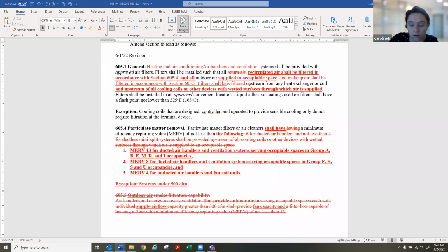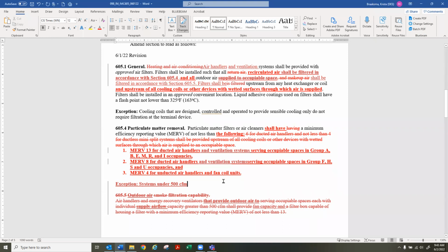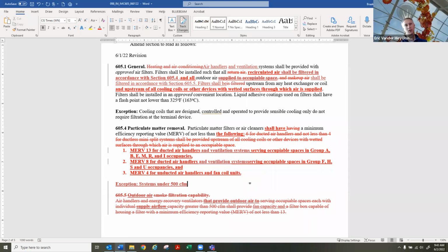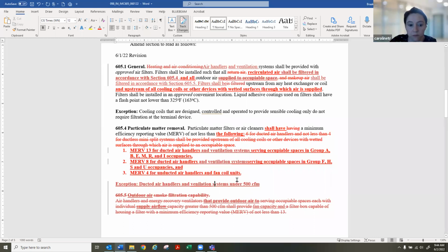Because essentially the MERV 4s aren't doing anything from a health standpoint. I'm assuming you don't want to exclude them from any filtration, though. Correct. What minimum do you want to specify? It's going to be MERV 8 for correlation. The small systems have to be MERV 8 for the residential Chapter 4 section. So I think systems under 500 CFM would need MERV 8 unless they're unducted. So you could say ducted air handlers and ventilation systems under 500 CFM shall have a minimum of MERV 8.